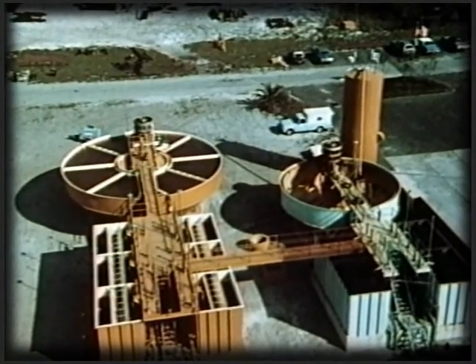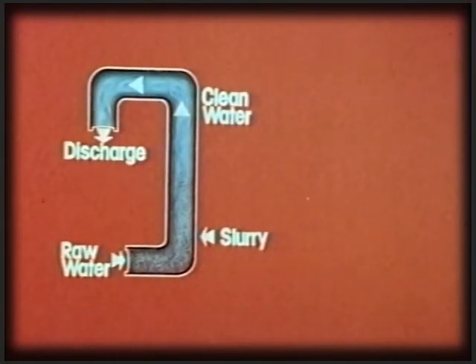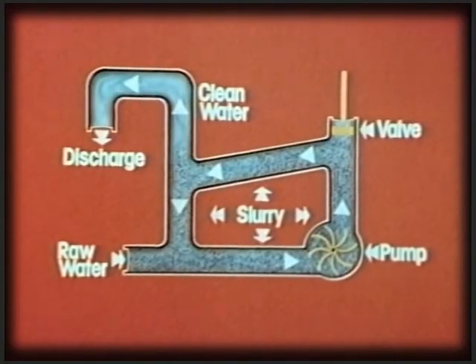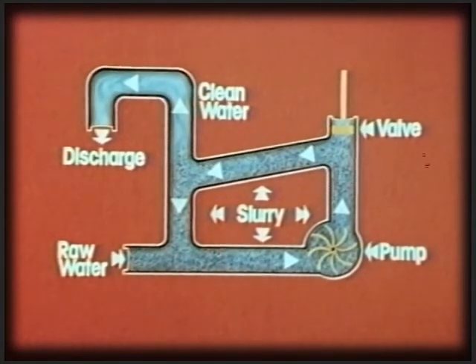What is dynamic separation? To illustrate, let's compare a process in which we feed raw water up through a mixture of slurry and chemicals to produce a flow of clean water. To maintain equilibrium, we can push the water through no faster than gravity will carry the solids downward. But the flow can be dramatically speeded up if we add a loop and a pump to recirculate the slurry. This is the principle of the Accelator using dynamic separation.